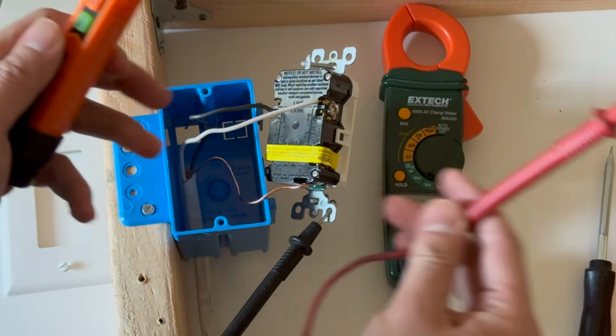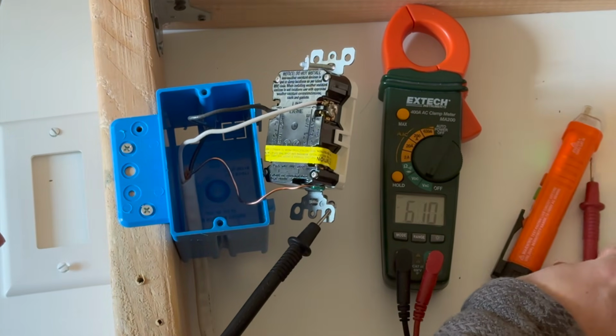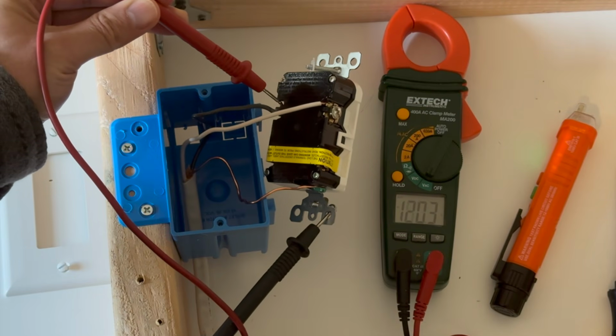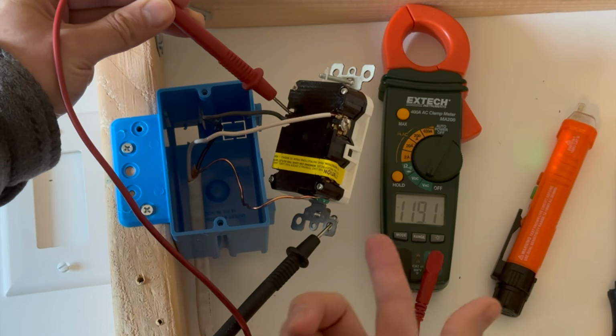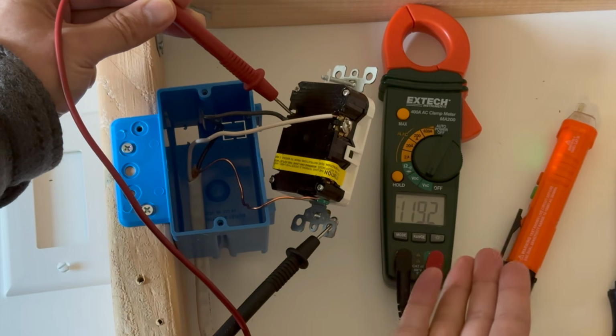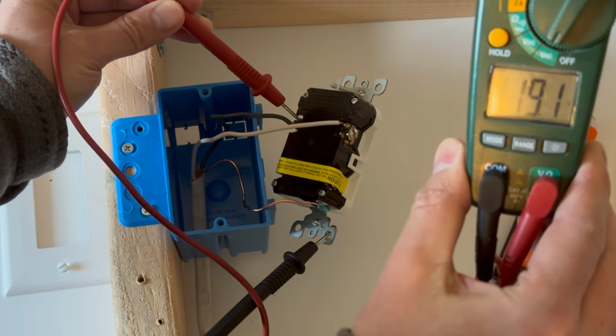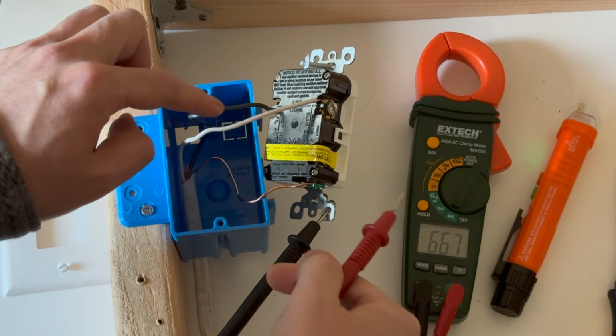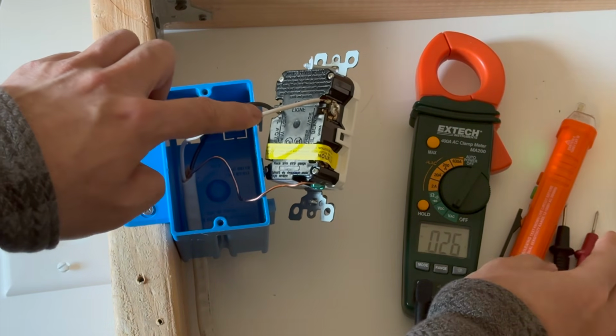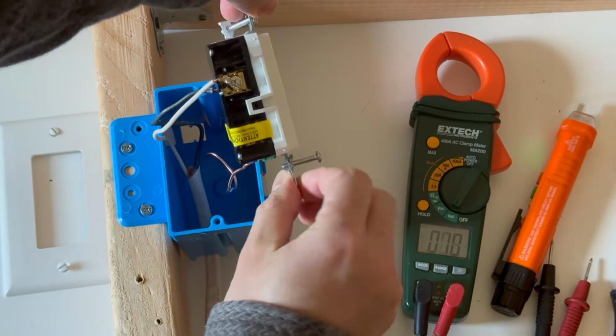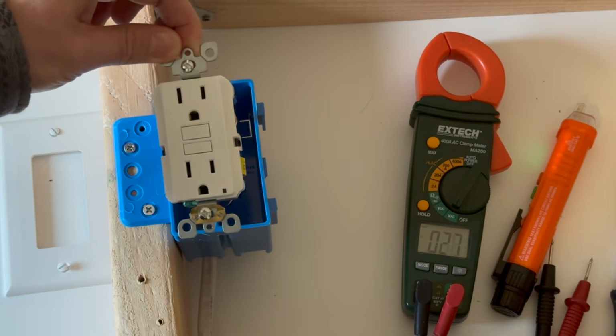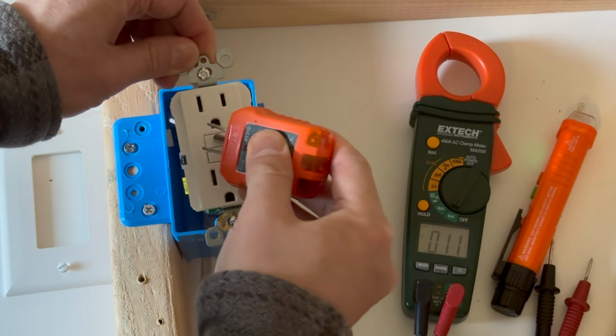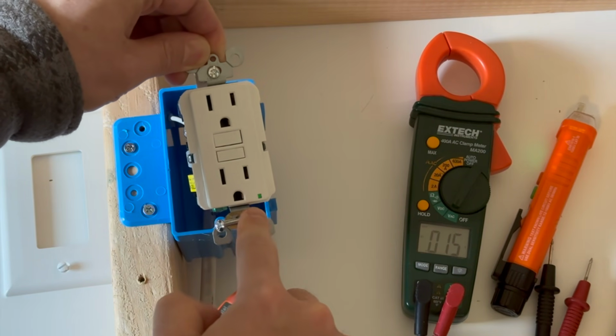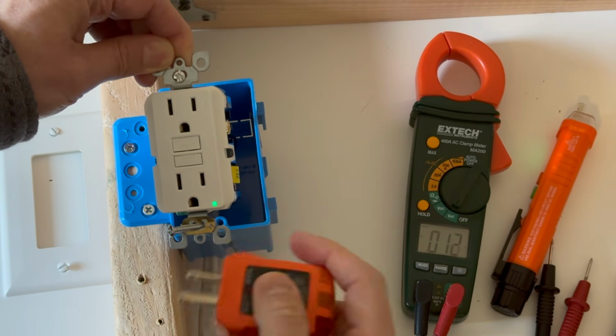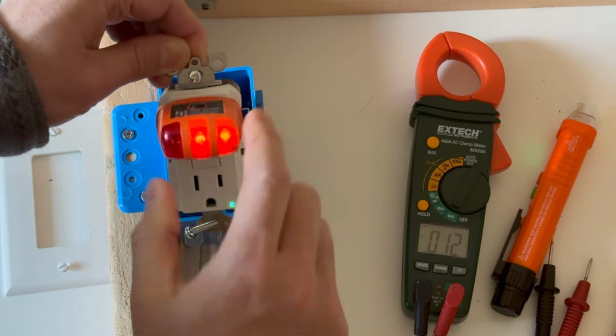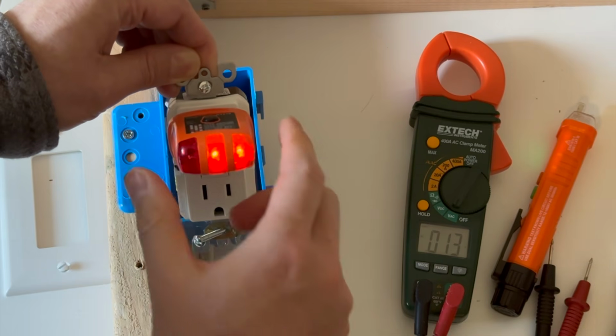So what I do, again, I read the voltage just to make sure that I have 120 volts or 115, 118, okay? So I have 119 volts. And now I know that the wires that are coming to the outlet have a power, and I try to reset it, okay? So I click the reset button. If it resets, you can see green light comes on, and I will plug in my plug tester to see if it's wired correctly. It has a power. Okay.